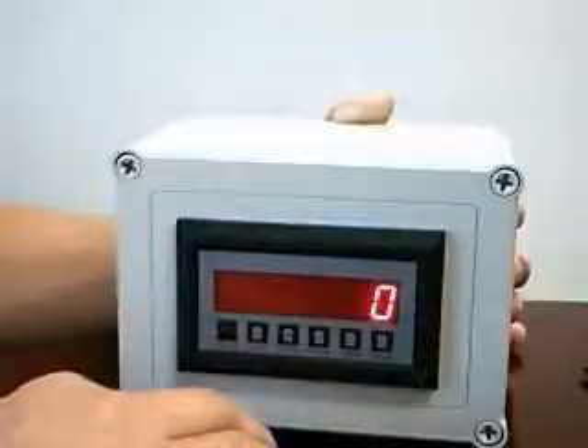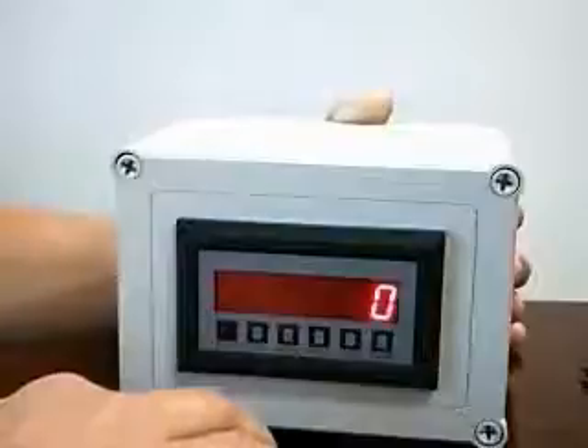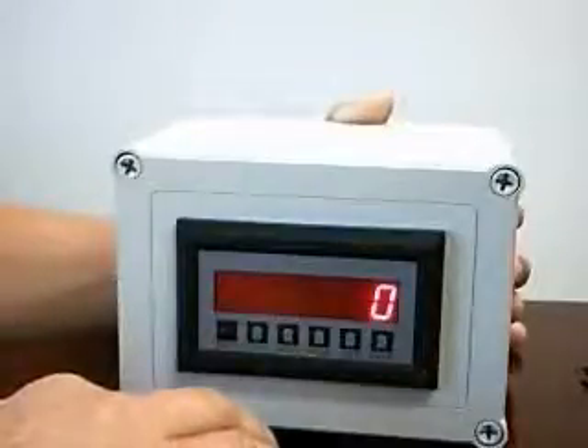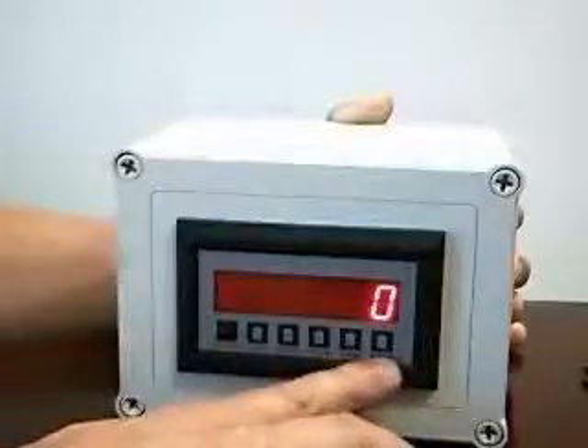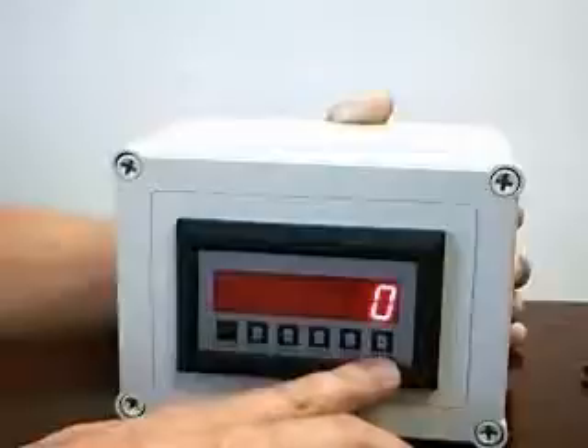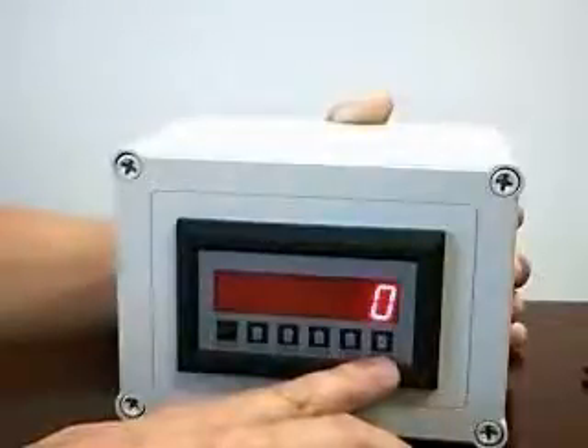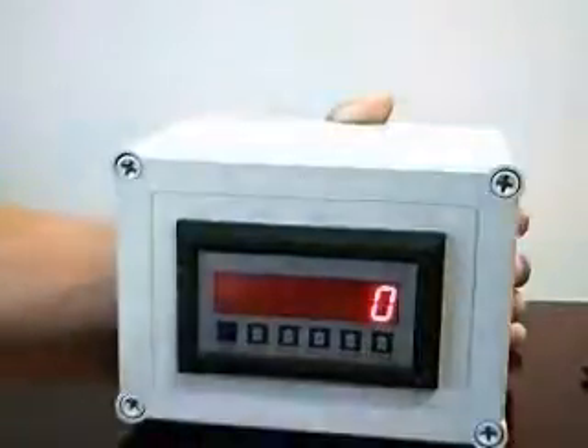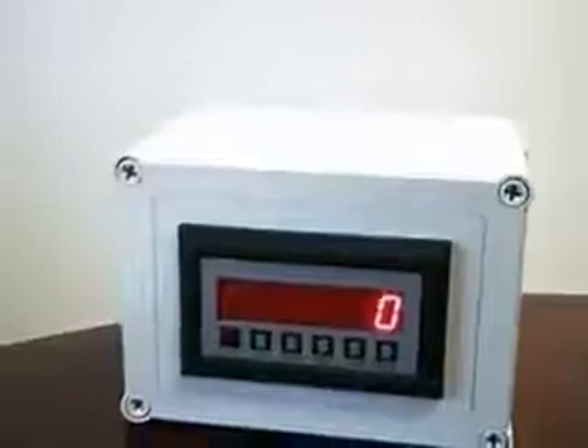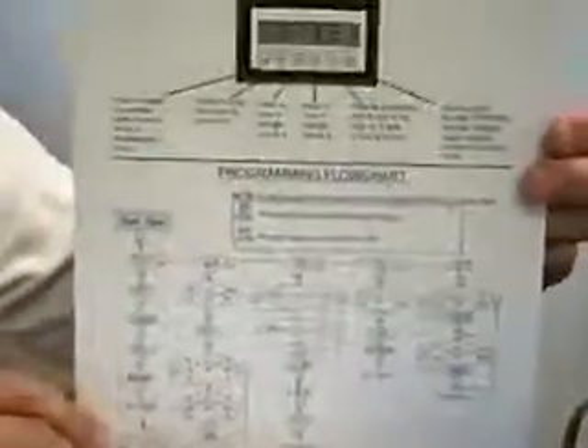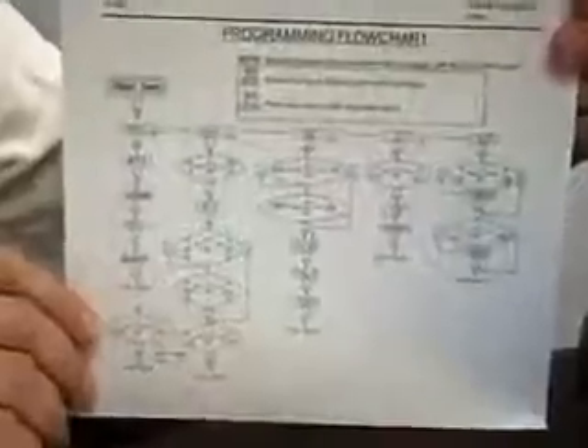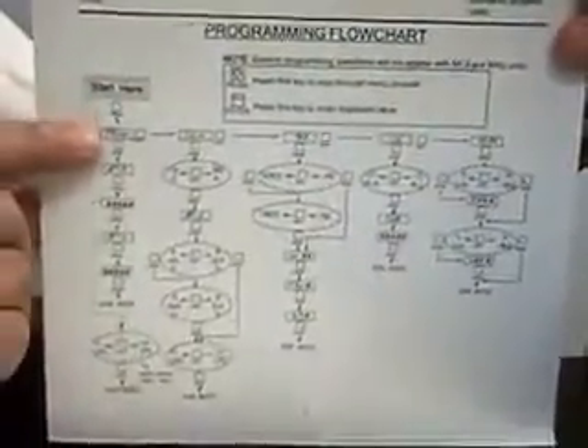Now, the next operation we may want to consider is how to change the operating mode to configure the instrument. This is done using the program button. Now, since the unit is currently unlocked, we're going to go to that sequence. I would like you to follow along by finding page 7 in your user manual. Here, you'll notice that there's a flow chart of the basic configuration of the instrument. It begins with a statement where it says start here, and you'll notice that there's small symbols indicating the key to depress to move into the various menus.